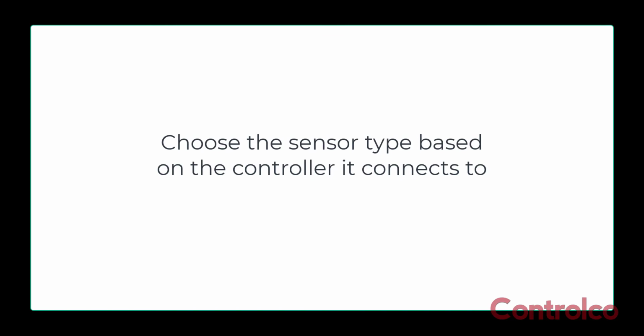Extremely important to look at the controller first before you go pick out your sensors. Time after time, we just order sensors and the controller changes and we've installed all of our sensors, we bring them back and the readings are just way off. Turns out that particular controller will only accept a 1,000 ohm sensor and we put a 10,000 ohm sensor on it. So that's a critical piece.